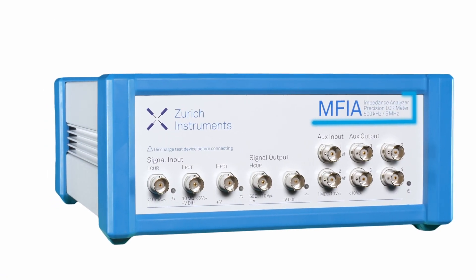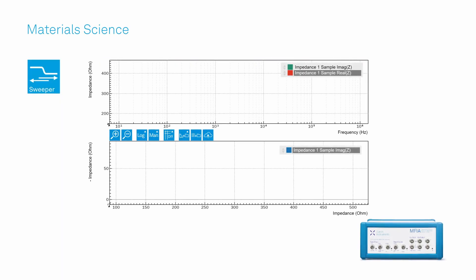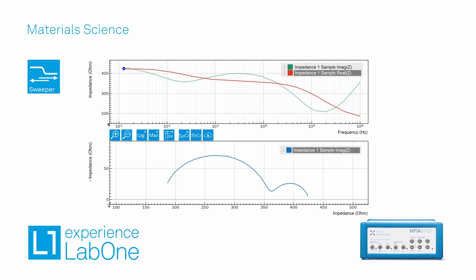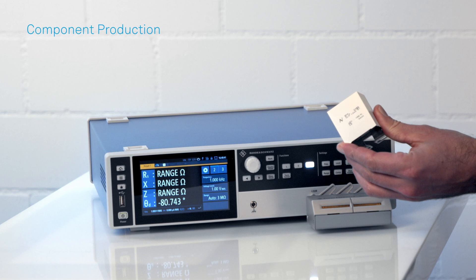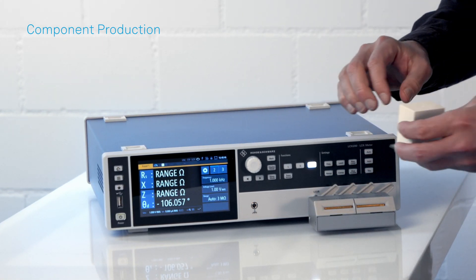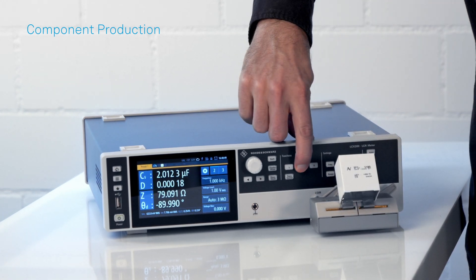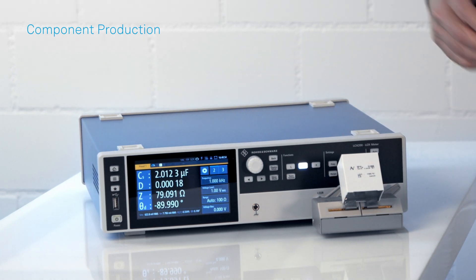Keep in mind some instruments do offer both capabilities in one. As a first example application, let's take material science. When sweeping the frequency, impedance spectroscopy yields the most detailed information of any electrical characterization. The MFIA is a good choice here thanks to the advanced LabOne sweeper function. For component and production testing or for more advanced measurements such as transformer characterization, you'll typically need to test at one frequency to check if a component passes or if the new development was successful. For such applications, consider an LCR meter such as the LCX.